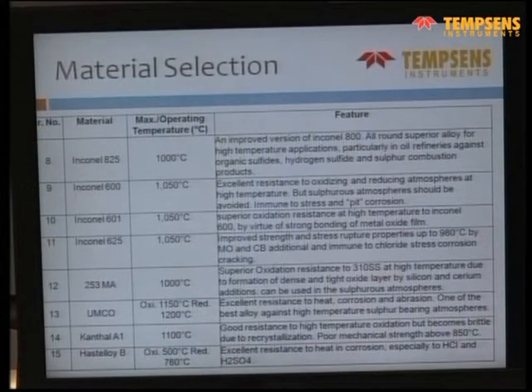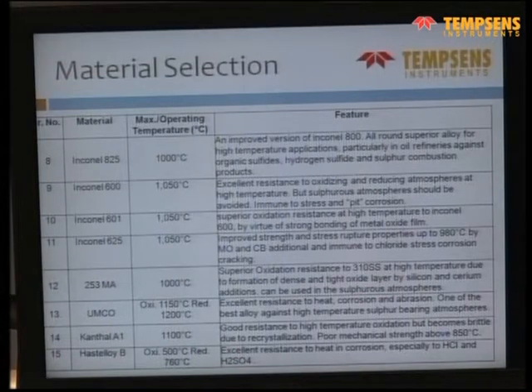Now coming to other materials like Inconel 825, Inconel 600, Inconel 601, Inconel 625. These are all Inconel materials. For example, Inconel 825 is better for hydrogen sulfide and organic sulfide applications or refinery applications. Inconel 600 is a good material for oxidizing atmospheres. Inconel 601 has better oxidation resistance at high temperature, because of the strong bonding of the oxide layer. Then Inconel 625 is used mainly in the nuclear industry. Inconel 625 is used for high temperature.